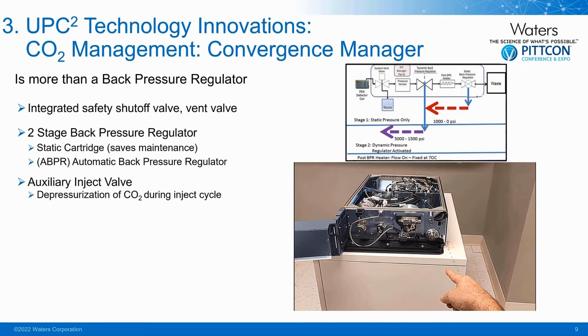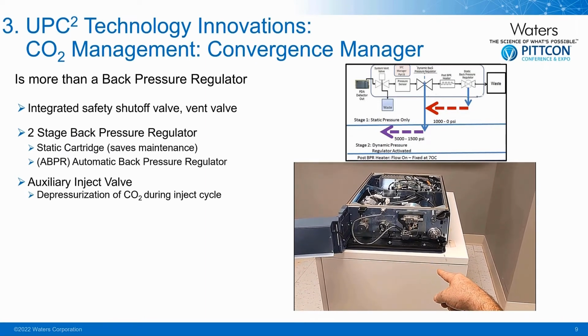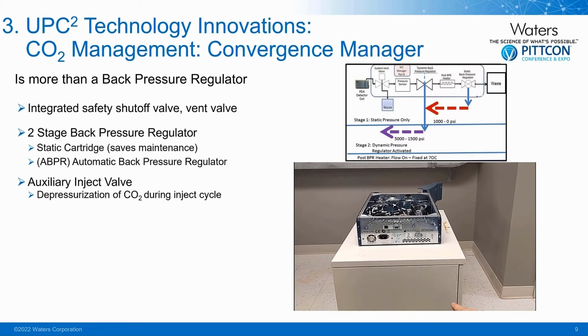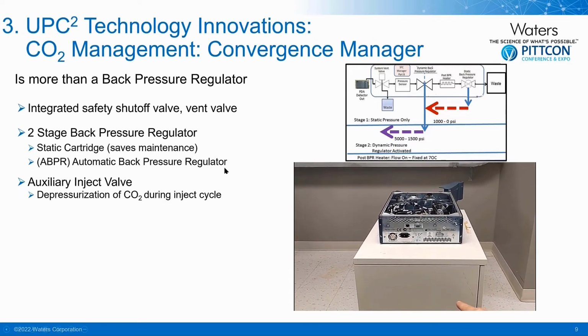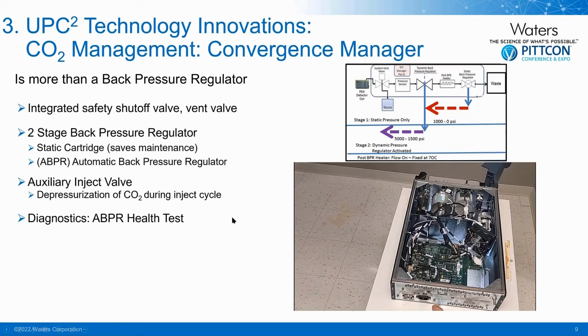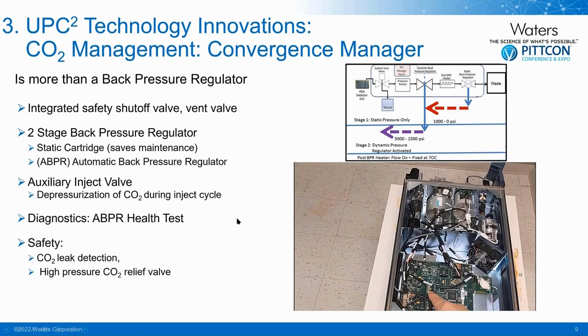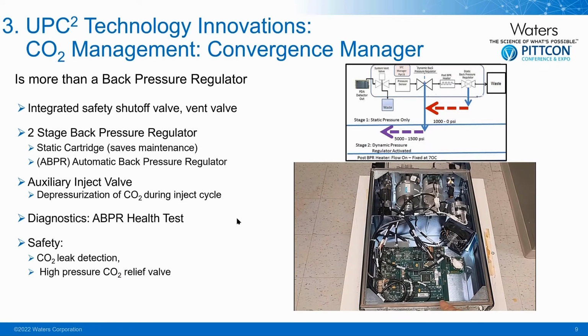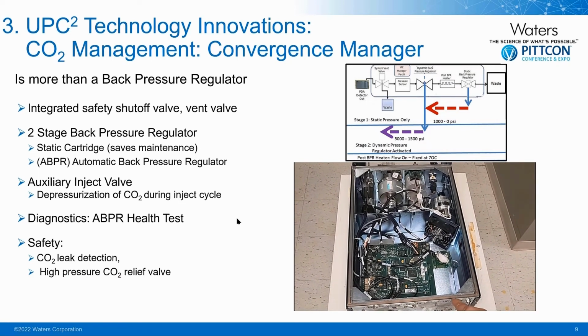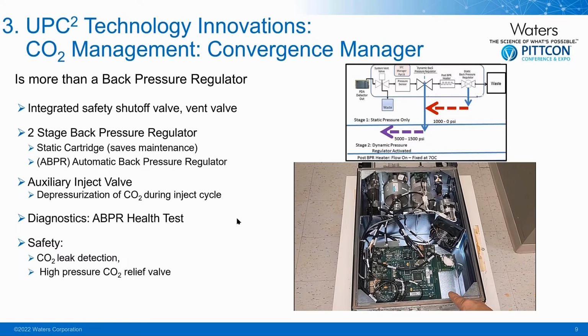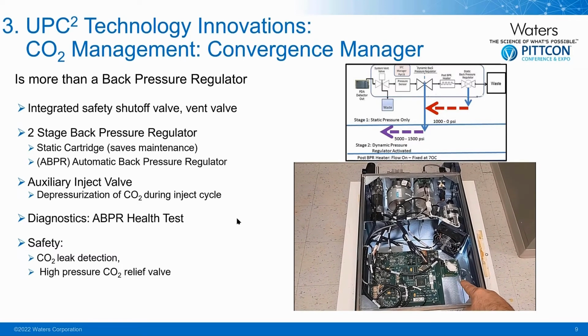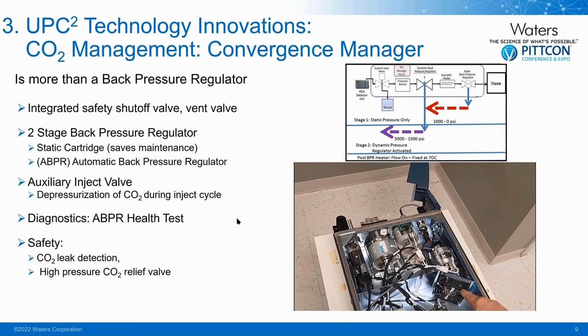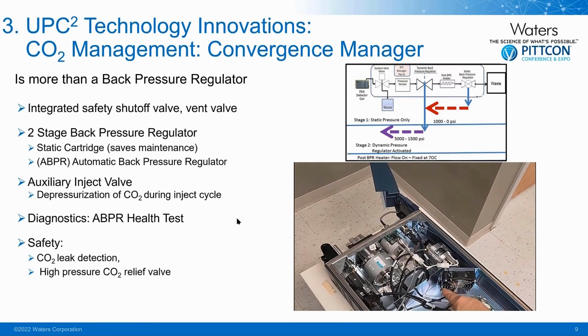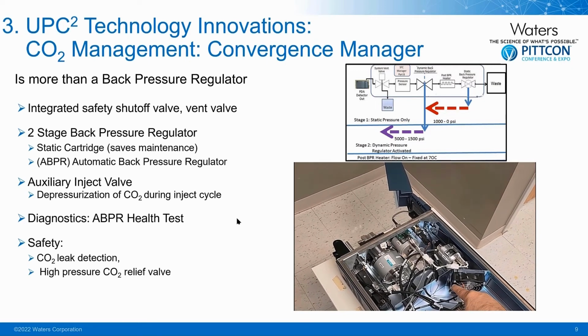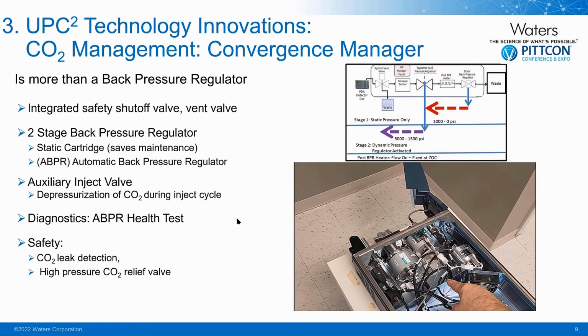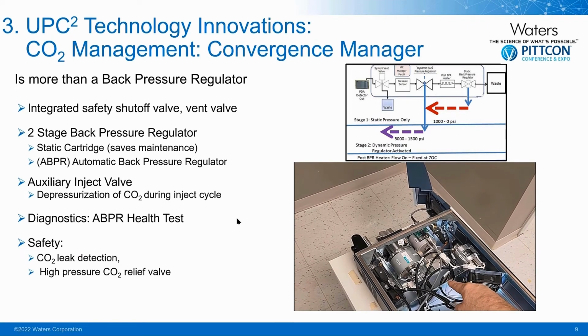The next piece is it also has an auxiliary inject valve, which aids in depressurization of the CO2 during the inject cycle. In addition, there's a diagnostics ABPR health test. And finally, for CO2, there's a leak detection, which I'm showing you right now. That's that white disc. If there's any type of leak, it will shut off the system. In addition, there is a high pressure relief valve that if the incoming pressure from CO2 goes above 1200 psi, it will vent out and release, so it does not overpressurize the system.